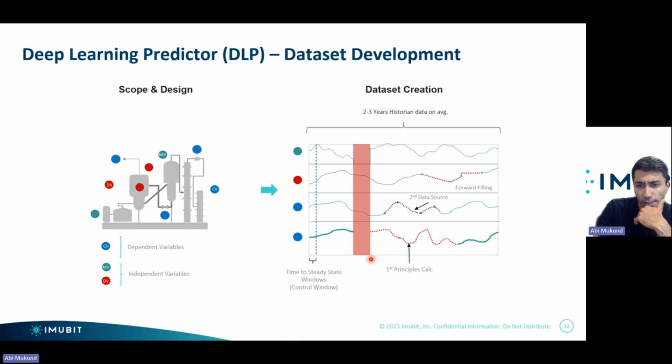So you can see here, a process expert has cleaned out the data set. They removed an outage period over here. And when you remove an outage period for a single tag, it's going to have to delete that entire window because the model's not going to train if it's missing one variable in this data set. But then oftentimes we see data compression. That's very common. So you can make some decisions on filling in that data set.